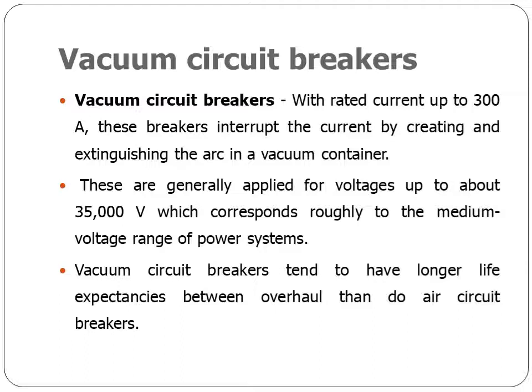First, we'll discuss vacuum circuit breakers. Vacuum circuit breakers with rated current up to 300 amps. These breakers interrupt the current by creating and extinguishing the arc in a vacuum container. These are generally applied for voltages up to 35,000 volts, which corresponds roughly to the medium voltage range of power systems. Vacuum circuit breakers tend to have longer life expectancies between overhauls than air circuit breakers.